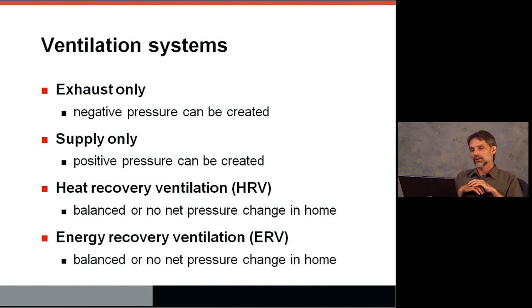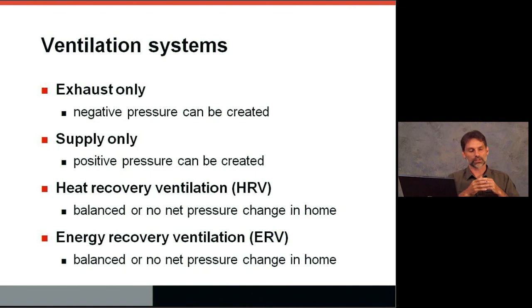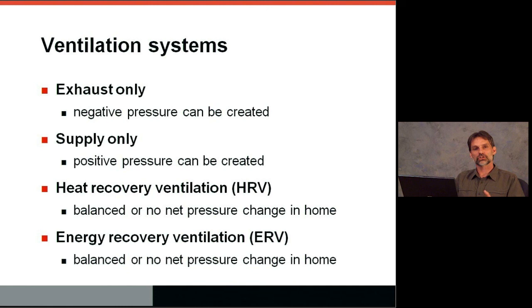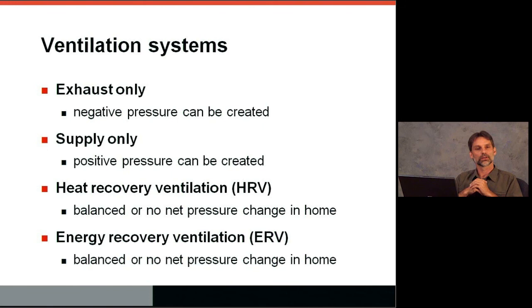Ventilation systems: we have exhaust-only, supply-only, heat recovery ventilators (HRVs), and energy recovery ventilators (ERVs) — they all do slightly different things. Exhaust-only systems are bathroom exhaust fans. Many Wisconsin Energy Star homes have exhaust-only ventilation — they rely on a continuous-duty exhaust fan with a very low, quiet rating and their houses operate just fine without upgrading to a balanced ventilation system.